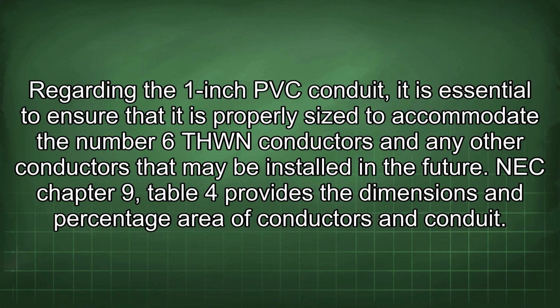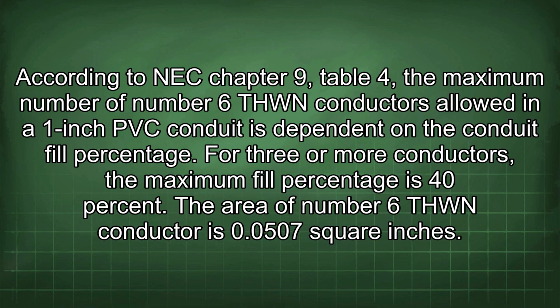Regarding the 1-inch PVC conduit, it is essential to ensure that it is properly sized to accommodate the number 6 THWN conductors and any other conductors that may be installed in the future. NEC Chapter 9 Table 4 provides the dimensions and percentage area of conductors and conduit. According to NEC Chapter 9, Table 4, the maximum number of number 6 THWN conductors allowed in a 1-inch PVC conduit is dependent on the conduit fill percentage. For 3 or more conductors, the maximum fill percentage is 40%.